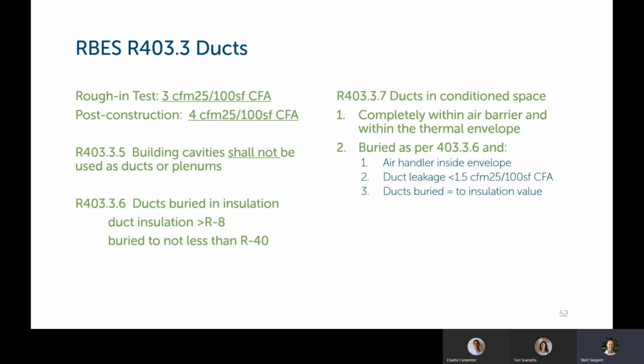So the rough-in test, if you want to test your ducts at rough-in, the limit is 3 CFM 25 per 100 square feet of conditioned floor area. A post-construction test would be 4 CFM 25 per 100 square feet of conditioned floor area. Also, there's provisions that building cavities shall not be used as ducts or plenums. I think in prior versions, it was okay to use building cavities as a return plenum, but that's no longer the case.